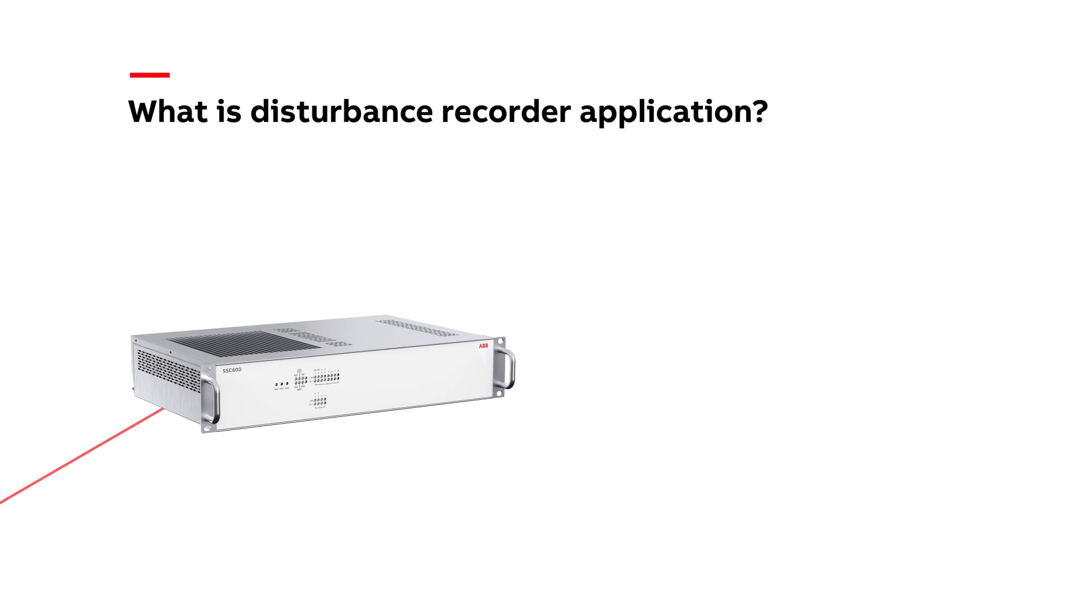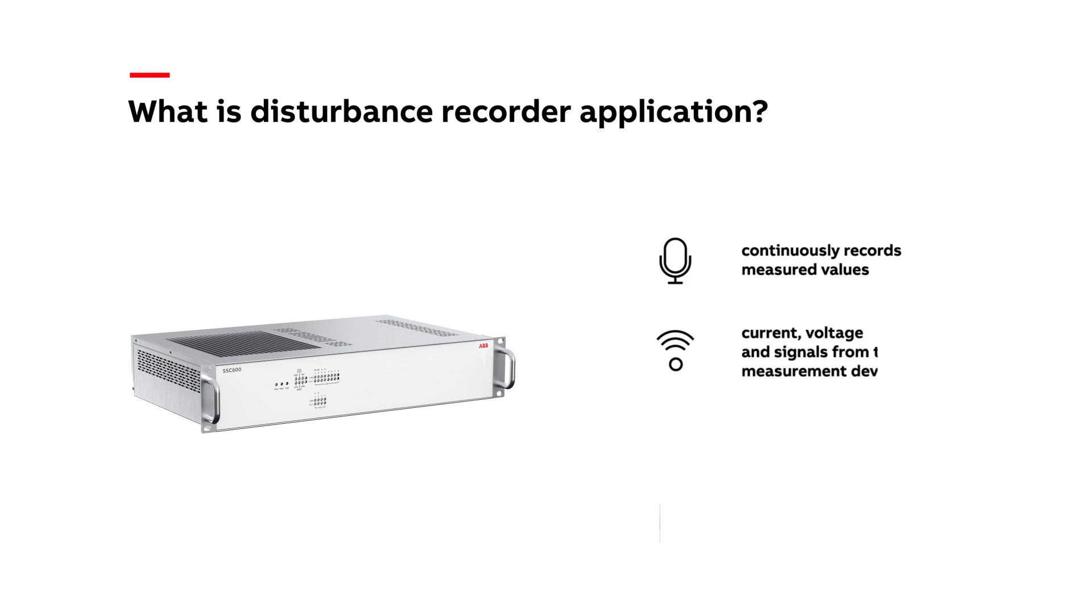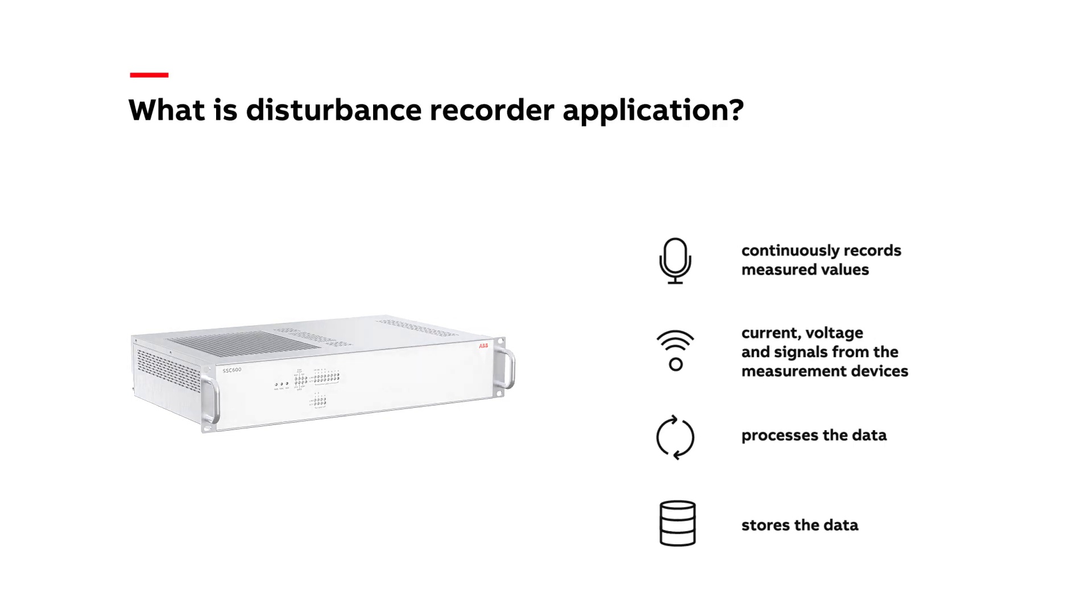A disturbance recorder is an application or specific device that helps us understand what happened in the network. It continuously records measured values—current, voltage, and signals from the measurement devices—processes the data, records and stores it in case triggering happens. It also helps us analyze the impact on the equipment and on the grid, and we can prevent it from happening again.